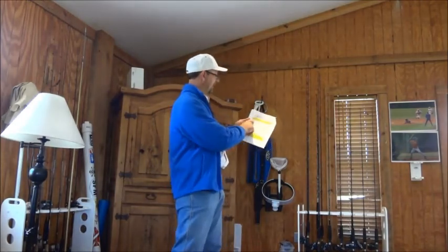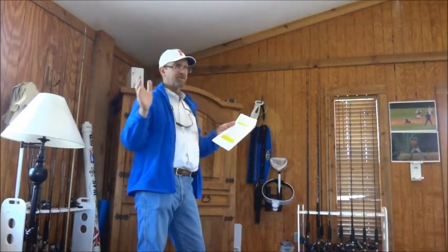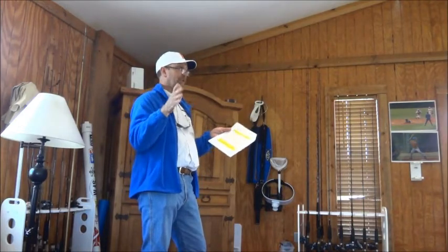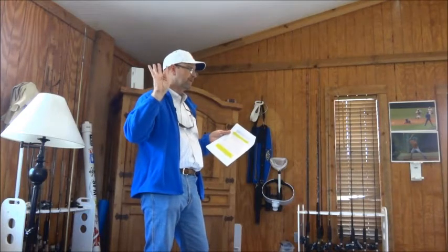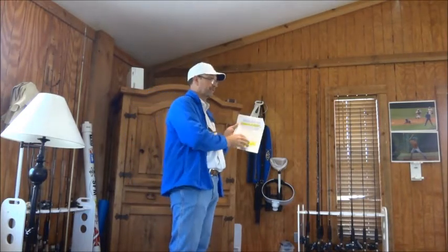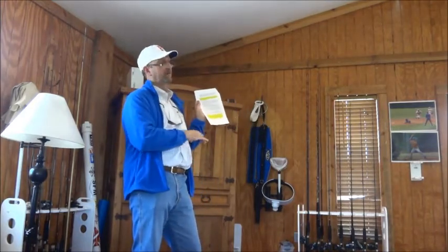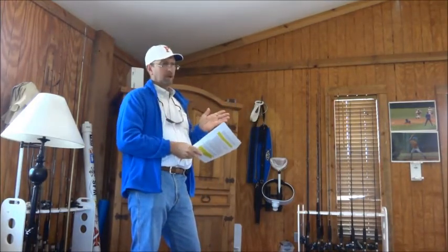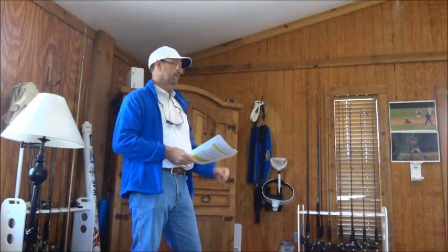So then they give you some answers on this, review the accuracy of the meters that have been used, and that's why the district wants you to analyze your meters. Every 5 years you're required to certify under conditions of your permit to get your meters recalibrated. I just did a ton of them. We just got involved in a bunch. It was a bad bunch. Half of the ones that we did were out of compliance.